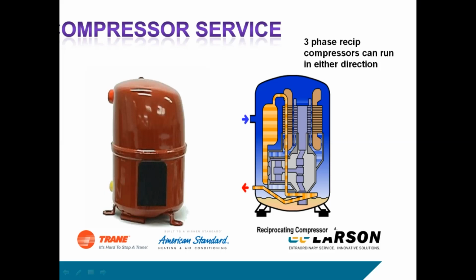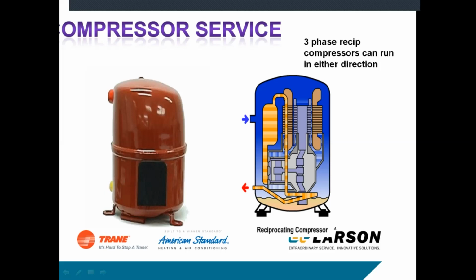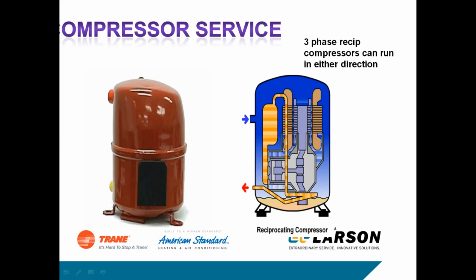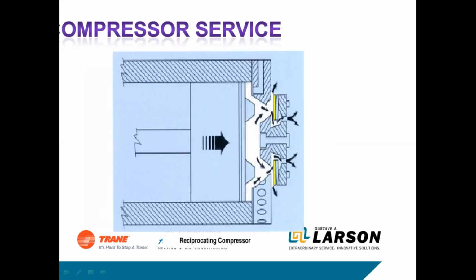So that was kind of nice. The new ones, the scrolls, are sensitive to that. You can't run a scroll backwards for very long anyway. They'll run for maybe 15, 20 minutes before they'll do something major and take themselves out. So that's why on the new ones we put phase protection on all of our commercial equipment.